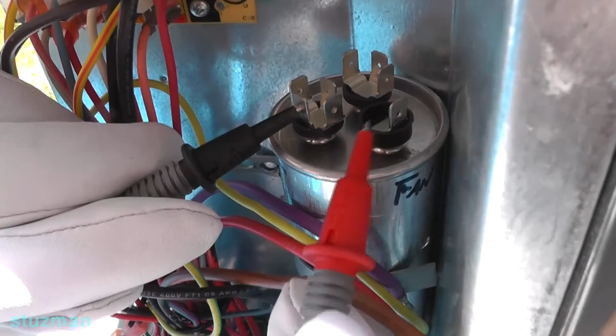Now, where I was on the fan, I'm going to move it back over to the Herm terminal. So now between the common and the Herm, what do we got? 38.16. Yeah, 38.16. Okay. Now, nominally, these two capacitors should be reading 40 microfarads and also 5 microfarads. So the one for the 40 microfarads might be a little bit low. These capacitors should have a plus or minus 6% tolerance. So let's see, if we take 6% of 40, that's 2.4. We take 2.4, subtract it from 40, we get 37.6.